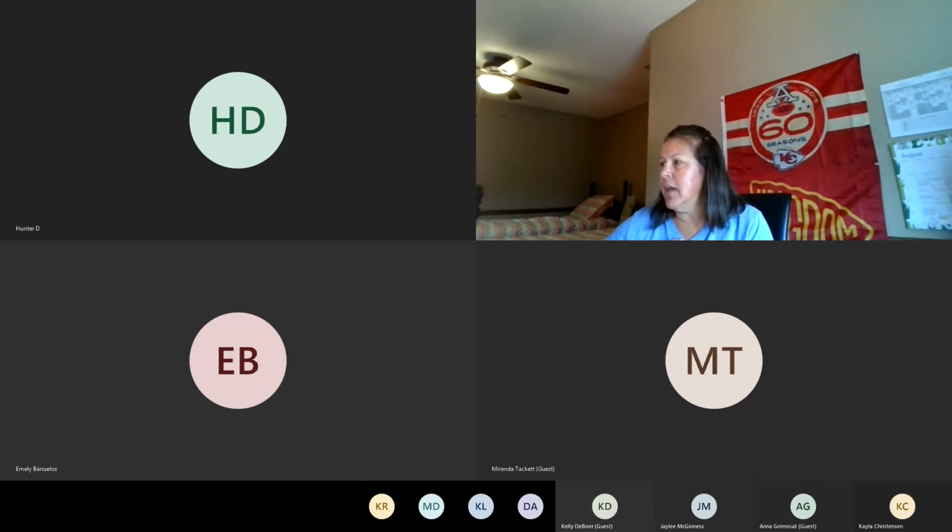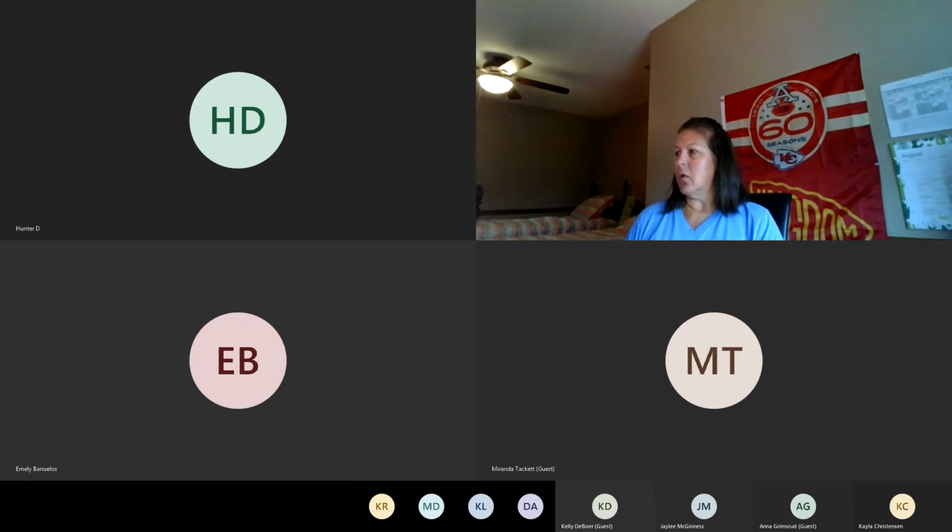What I did here is just kind of summarize the production of X-rays. So electricity supplies the energy to the X-ray machine from the wall at 110 or 220. The current is then directed to that filament circuit, which is our low voltage, and we use that step-down transformer to convert those 110 or 220 volts down to 3 to 5 to create enough energy at that filament to create our electron cloud around that wire.